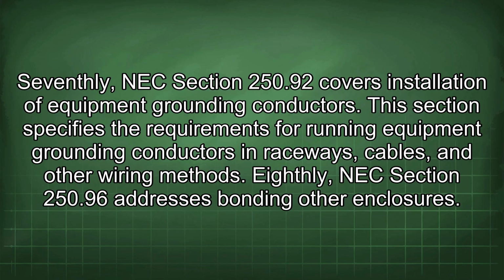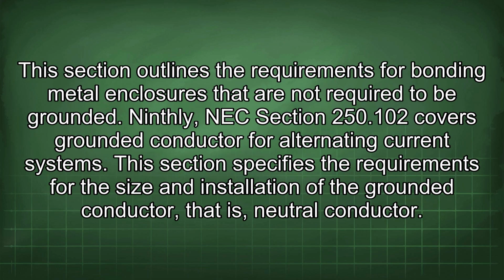Seventhly, NEC Section 250.92 covers installation of equipment grounding conductors. This section specifies the requirements for running equipment grounding conductors in raceways, cables, and other wiring methods. Eighthly, NEC Section 250.96 addresses bonding other enclosures. This section outlines the requirements for bonding metal enclosures that are not required to be grounded.